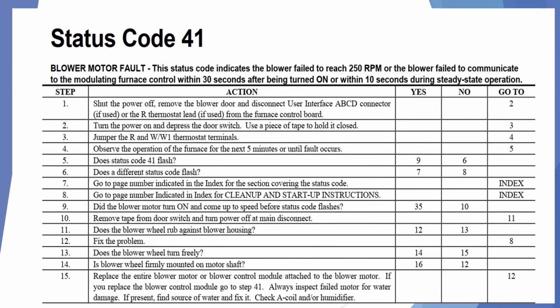This particular furnace is showing a fault code of 41, which means that it is a blower motor fault. So 41 is indicating that the blower motor is not reaching 250 RPM, or the blower has failed to communicate to the modulating furnace control. It goes through some basic things like, is the blower wheel rubbing against the blower housing, things of that nature. Does the blower wheel turn freely? And then it's going to do the same thing that we said before. Either yes or no answers will lead you to a particular step that you need to go to to resolve the issue.